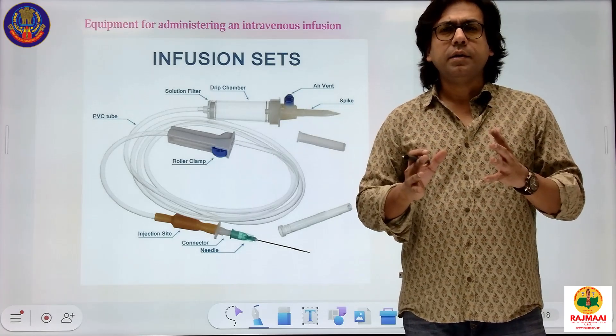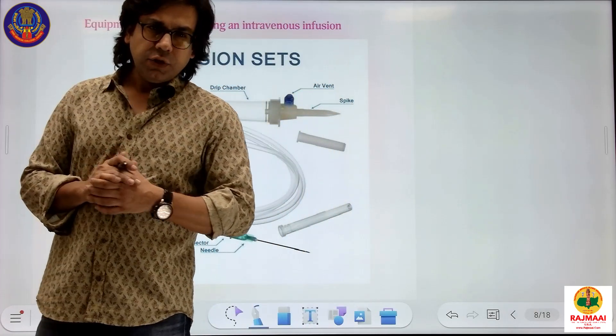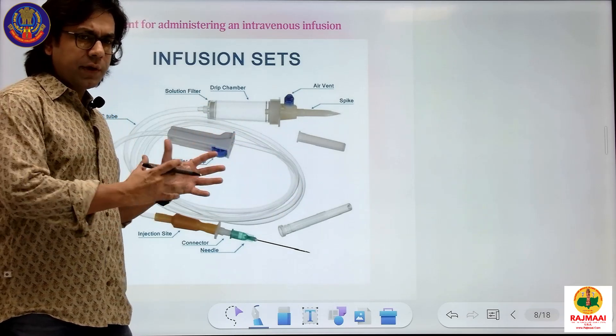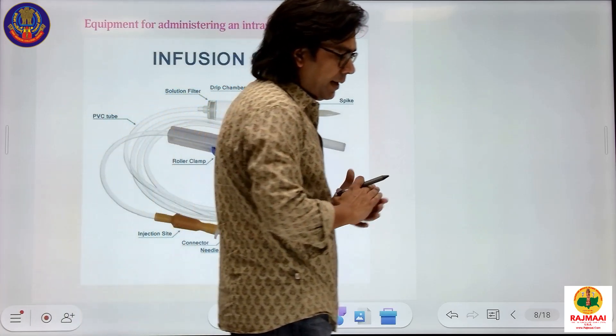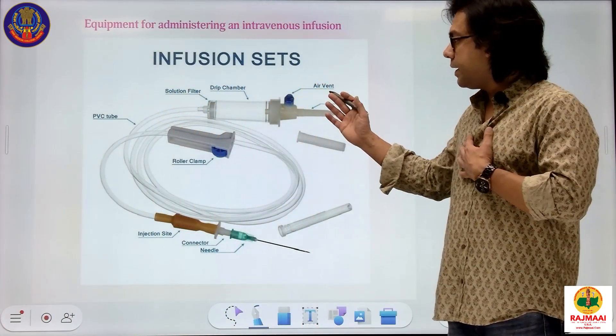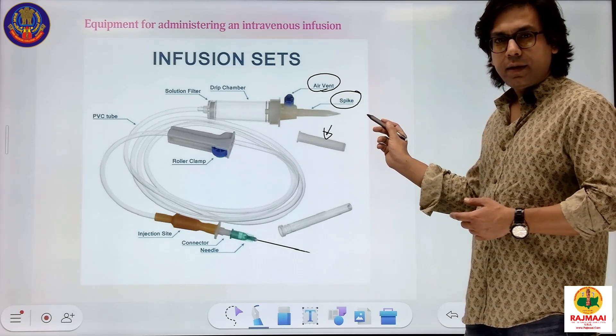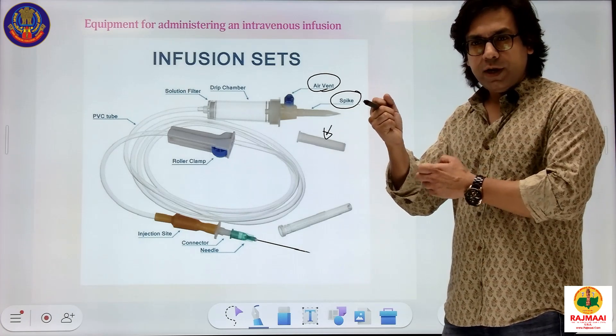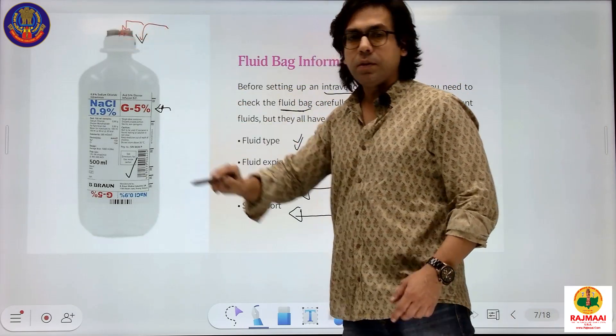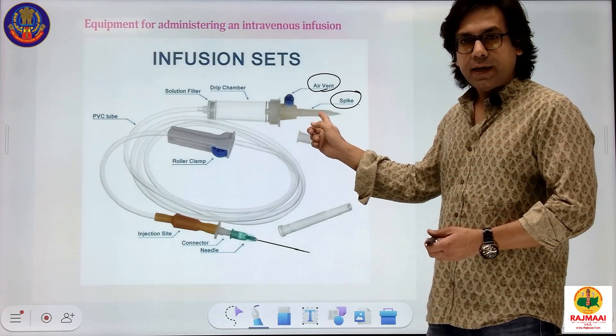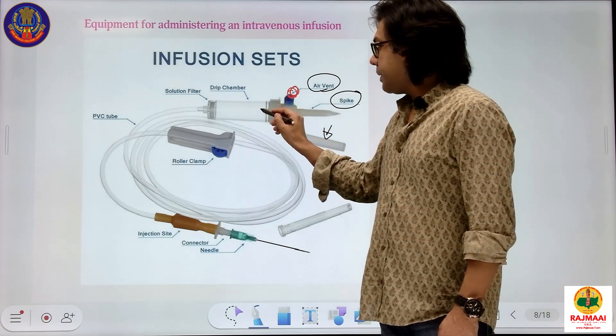The most important diagram of today's class is the infusion set. This infusion set is what is used to administer IV fluid — it connects the fluid container or solution container to the IV cannula. This type is called a vented infusion set, which has a vent. Looking at its parts: the spike and its covering cap — the spike is what pierces into the fluid bag through the spike port. Below that is the air vent, since this is a vented infusion set.